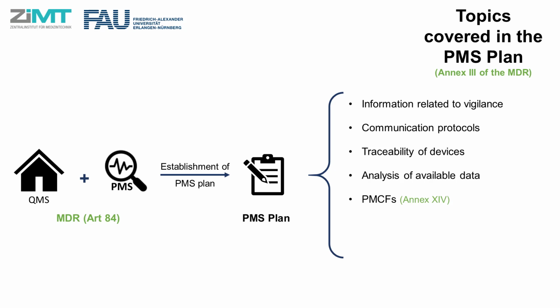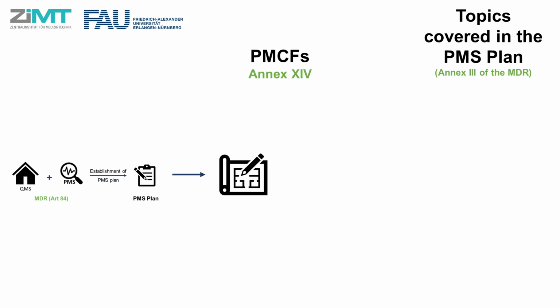Define effective tools to trace and identify devices. Describe procedures used to deal with feedback and complaints from the user, and include an analysis of available data on side effects and similar devices, and how the manufacturers distribute and import the medical device on the market. In the plan, the manufacturers shall also describe, if necessary, the production of their post-market surveillance report and their periodic safety update report, and a description of their post-market clinical follow-ups. The post-market clinical follow-ups, PMCF, are part of the post-market surveillance system of a company, and they are described in a dedicated plan.